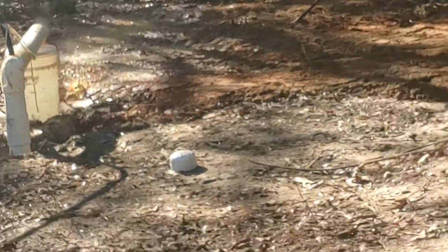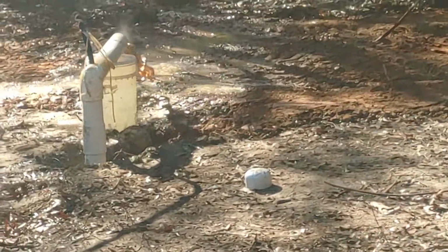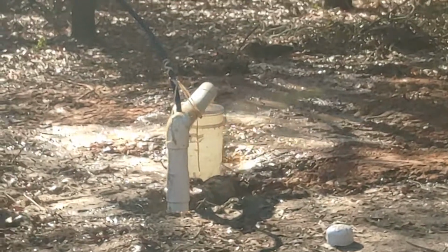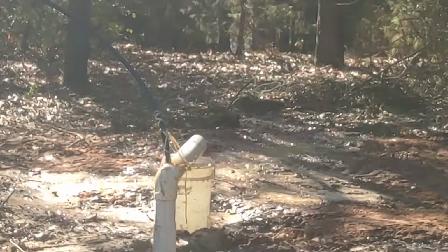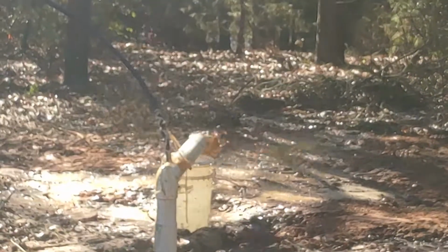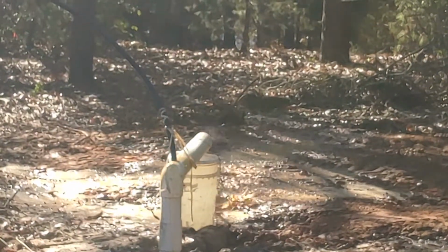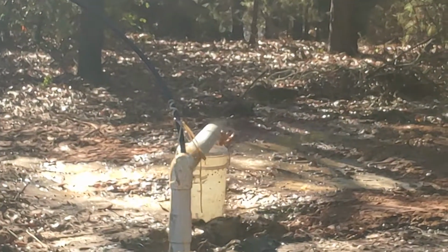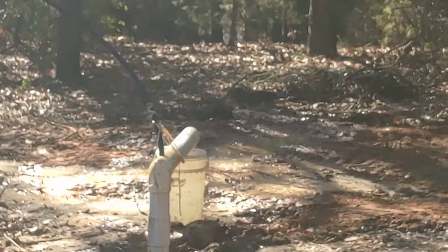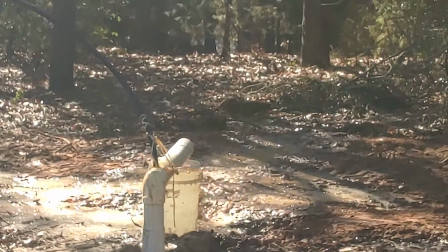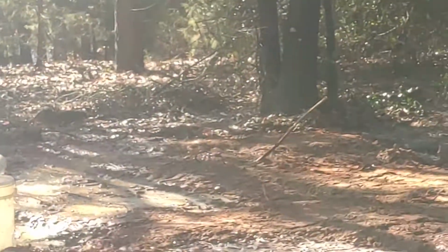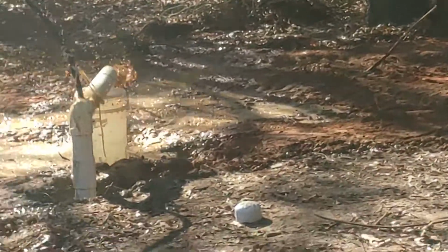So you pulled it out of the sand at the bottom. Just like I told you, sometimes that's all that happens. That's all you got to do to it. See how nasty the water is? That's your drilling mud. See that real clear stuff at the top? That's your head. That's your actual well water. Because the mud has encapsulated everything, it's heavier, so it's at the bottom, and your good water sits at the top. So it'll clear up even more than it was. I mean, it'll be crystal clear. You can drink it. So it'll clear all the way down to the cap at the bottom. Right now we're sitting at the cap.